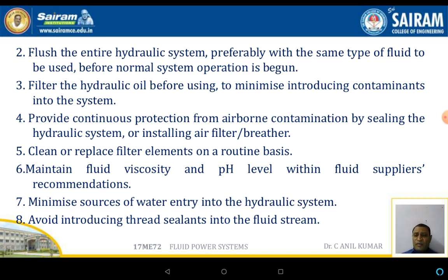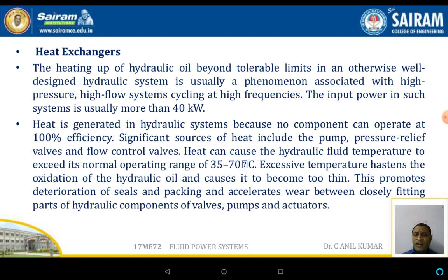Provide continuous protection from airborne contamination by sealing the hydraulic system or installing air filters or breathers at opening ends. Clean and replace filter elements on a routine basis. Maintain fluid viscosity and pH level within the fluid supplier's recommendations. Minimize sources of water entry into the hydraulic system and avoid introducing thread sealants into the fluid system, as these can introduce air and moisture contamination.